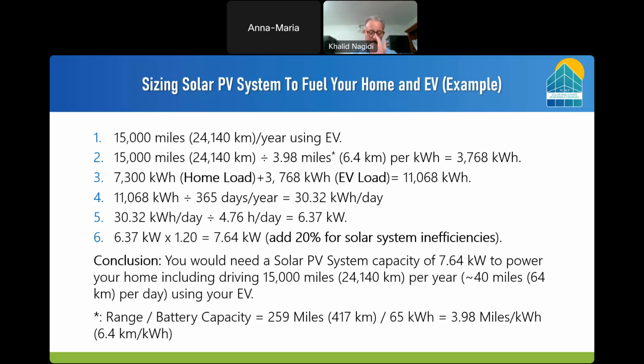Step number 6: because solar systems are not 100% efficient, there are many inefficiencies, from mismatch, to power losses, to cabling, to dust over your solar PV panel, to inverter and charge controller inefficiencies. All of those reduce the overall capacity of your solar system. In this case we applied a factor of 20% inefficiencies, so you take the number from step 5 and multiply it by 1.2 to account for the inefficiencies.